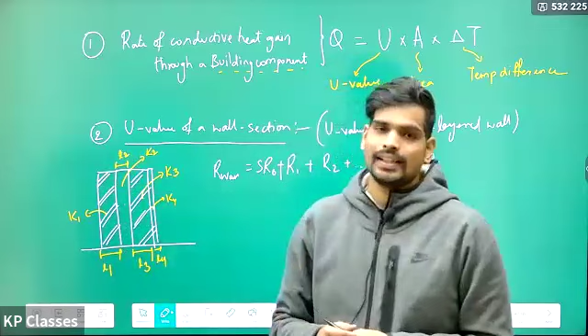So for any given layer, you can substitute L by K to find the value of the resistance of that layer. So you can rewrite the second formula. The other approach would be 1 upon the U value of the wall, because R is nothing but 1 by U. R and U values are reciprocal of each other. So you can write 1 by U as equal to the surface resistance of the outside surface plus, instead of R1, L1 by K1. Thickness divided by thermal conductivity is called resistance, plus so on up to Ln by Kn. You need to add L by K for all the layers and add the surface resistance of the inside and the outside surface. This is the final formula, an important formula which has been asked multiple times with 2 marks in the examination.